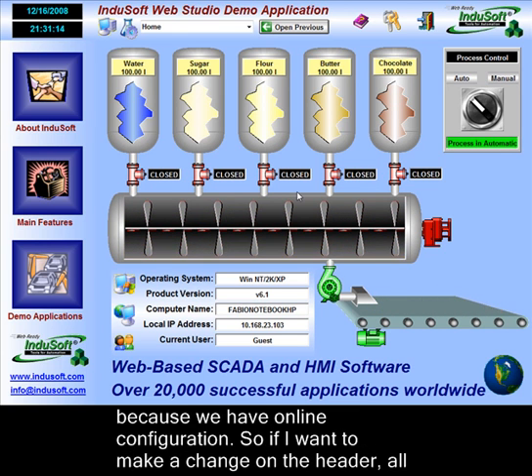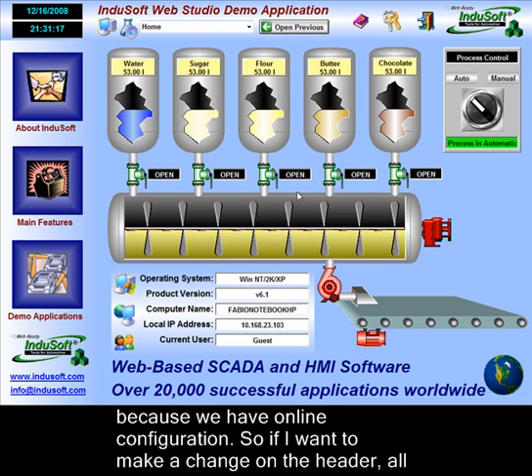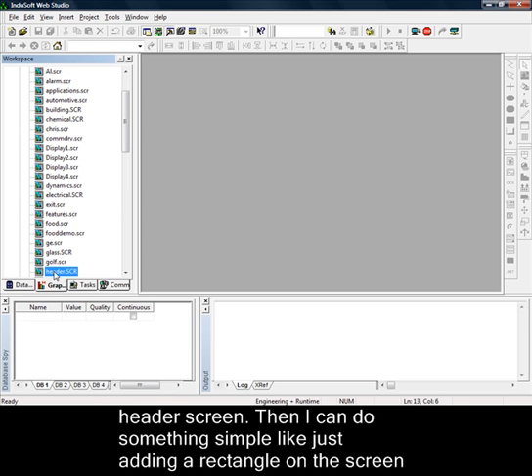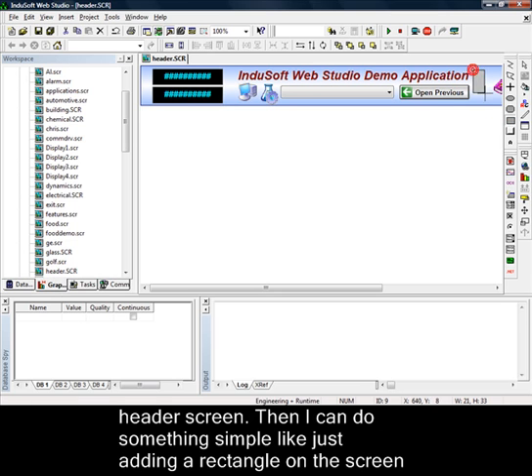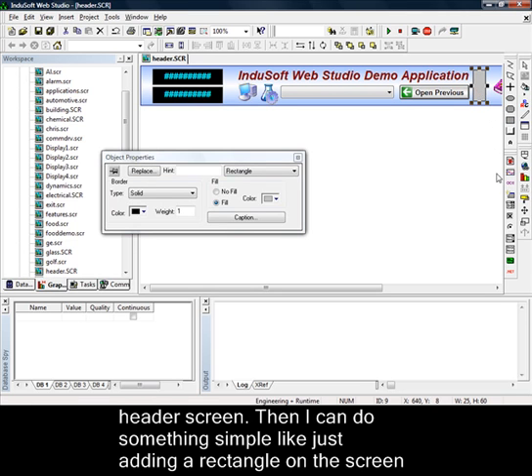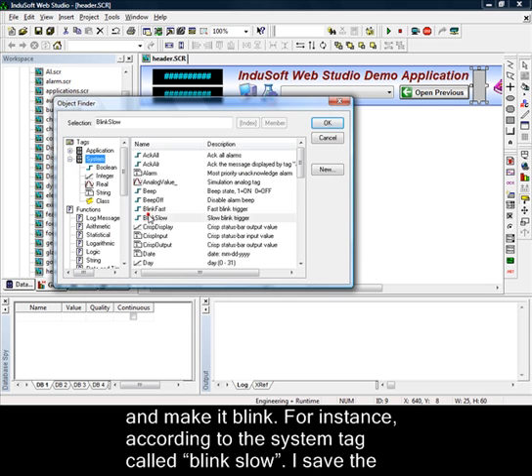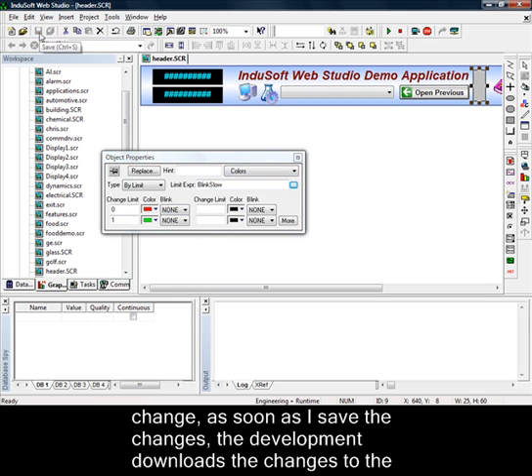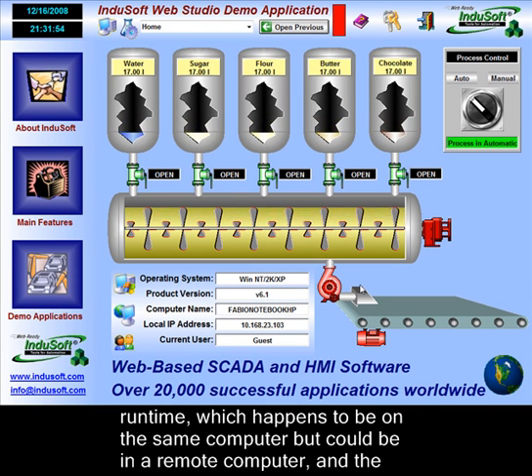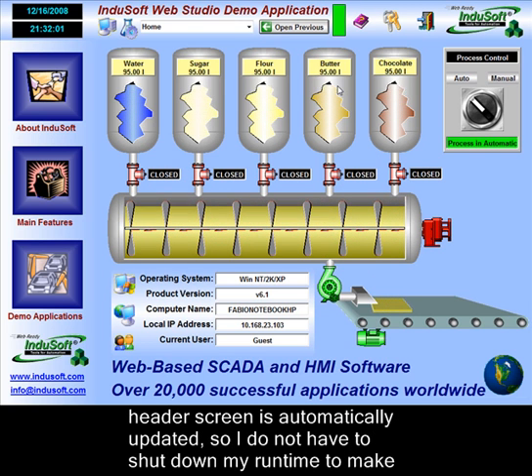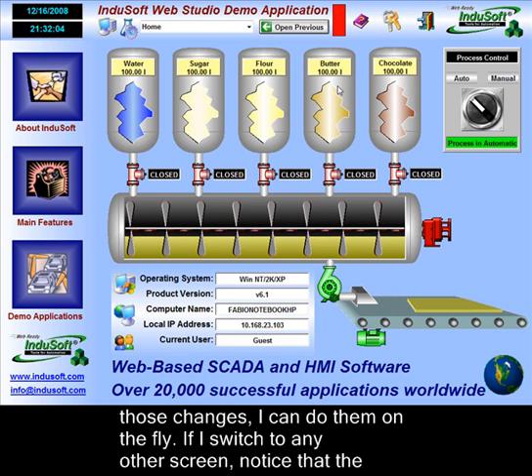I can do that even during the runtime because we have online configuration. So, if I want to make a change on the header, I switch to the development environment, select the graphics tab, screens, and then edit the header screen. I can do something simple like adding a rectangle and make it blink according to the system tag called blink slow. I save the change, and as soon as I save it, the development environment downloads the changes to the runtime — which could be on a remote computer too — and the header screen is automatically updated without shutting down the runtime.